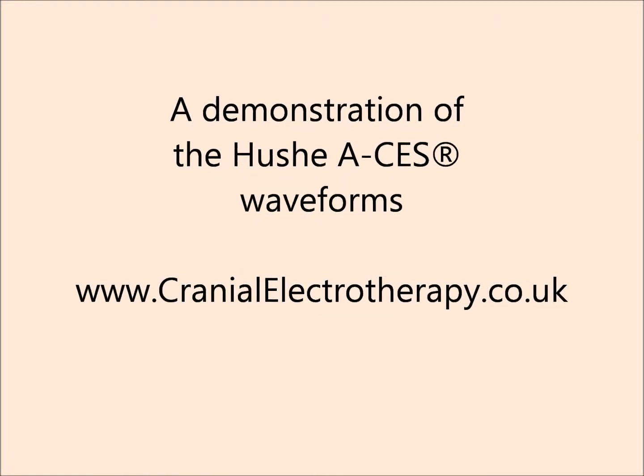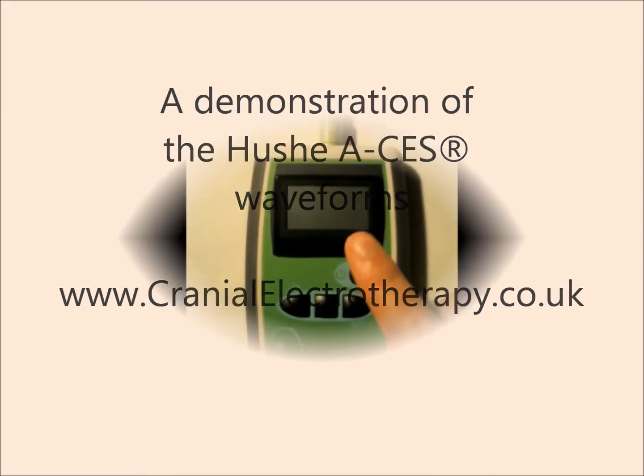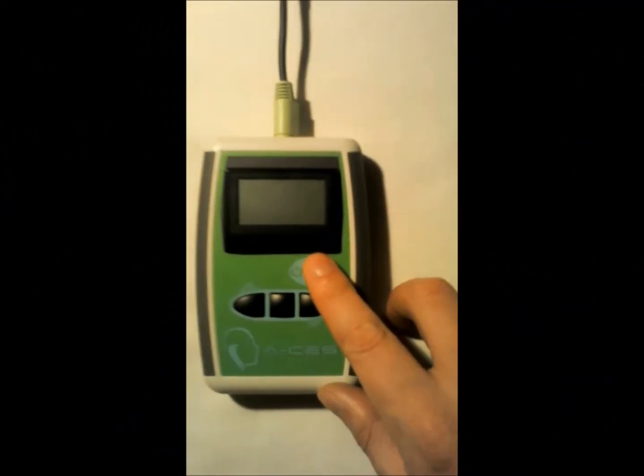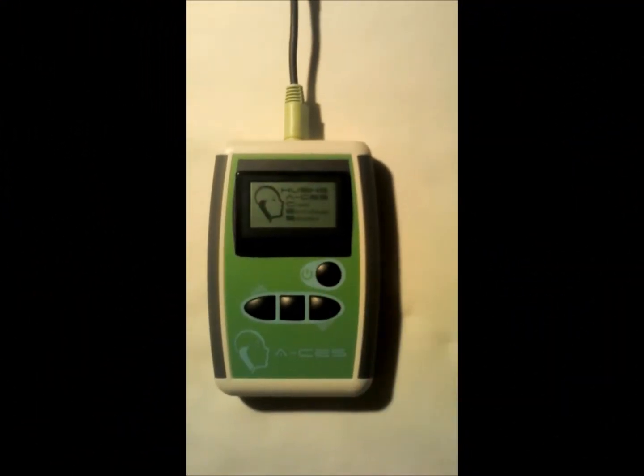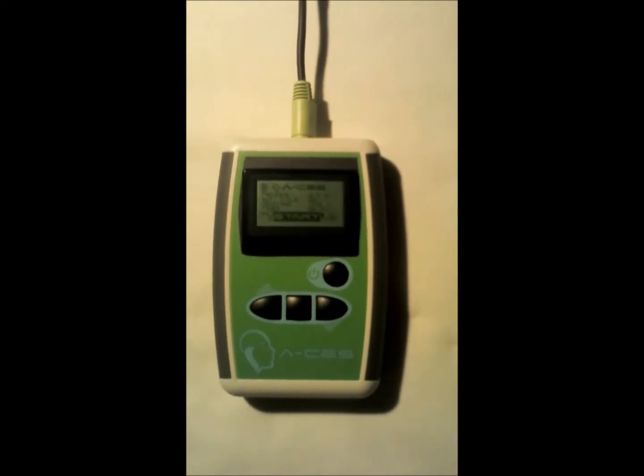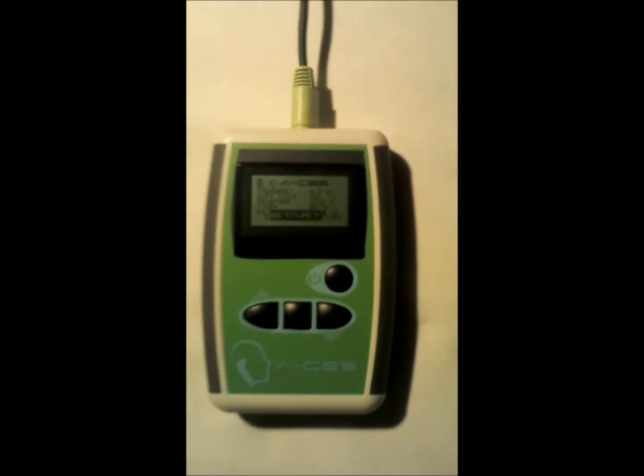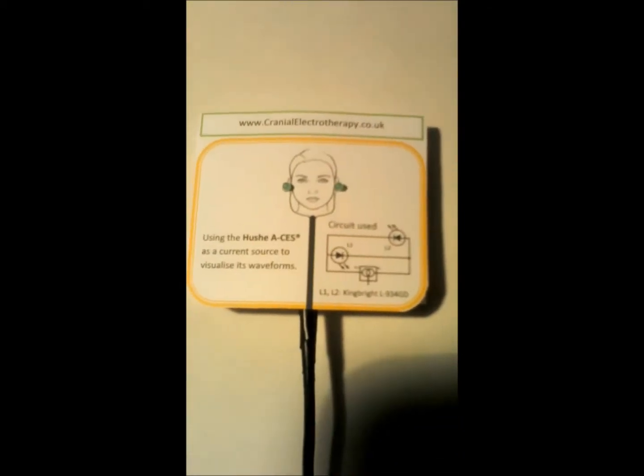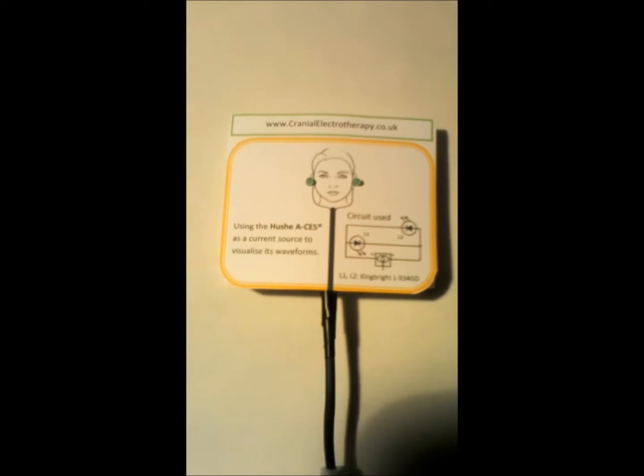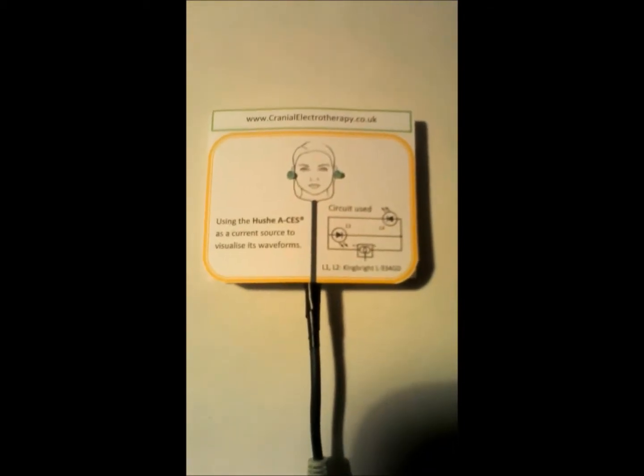Hello, I'm Chris James. This video will demonstrate the waveforms and output levels of the Hushe A-CES using a pair of light-emitting diodes, or LEDs, in place of the user. The Hushe A-CES generates a very low current output, which is barely sufficient to light a standard LED. For this reason, I'm using two low-power 3mm LEDs for this demonstration. A circuit diagram is provided in case you're interested.